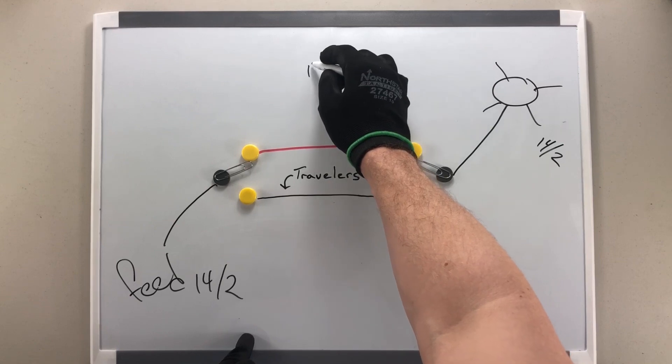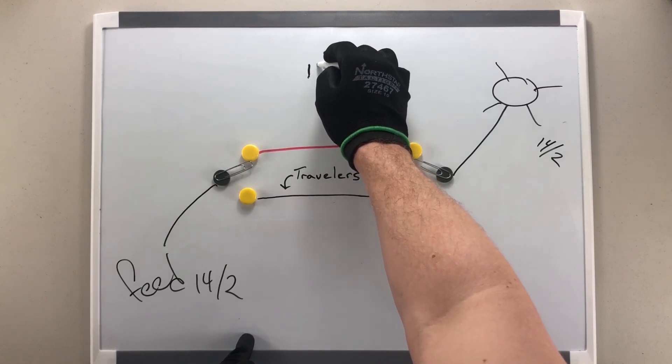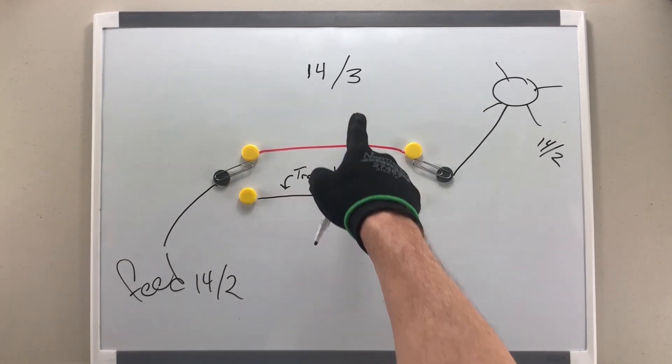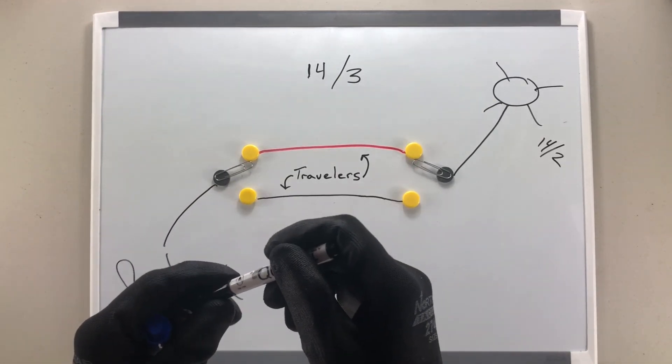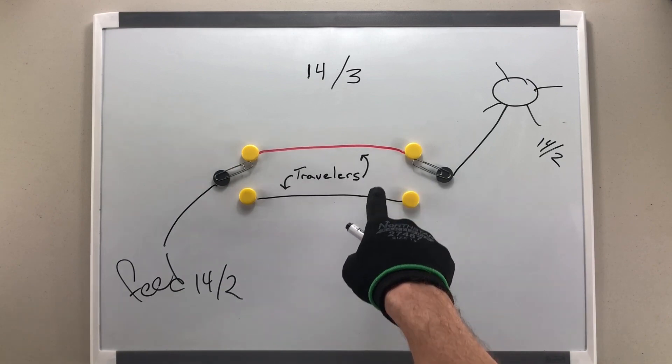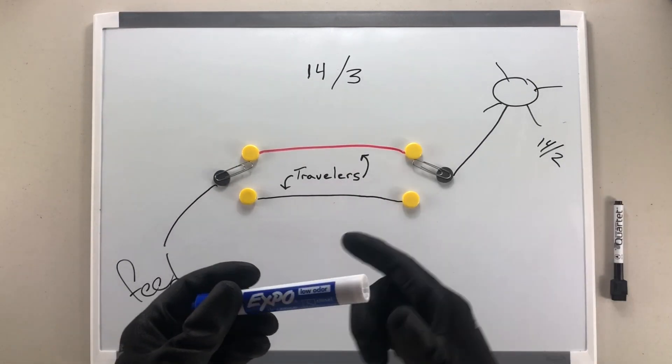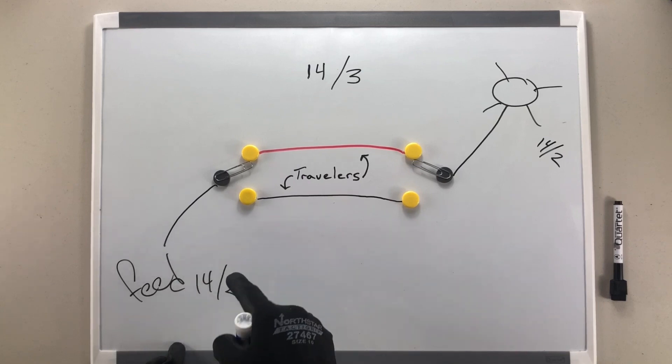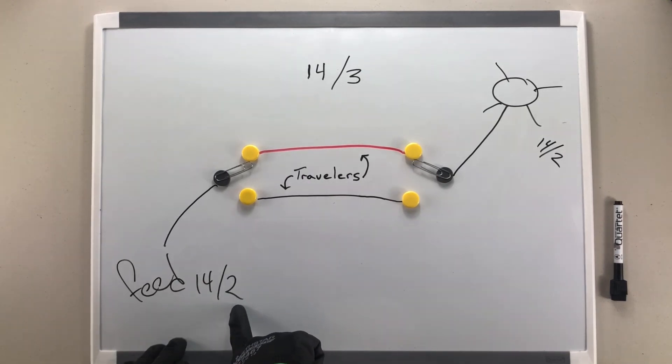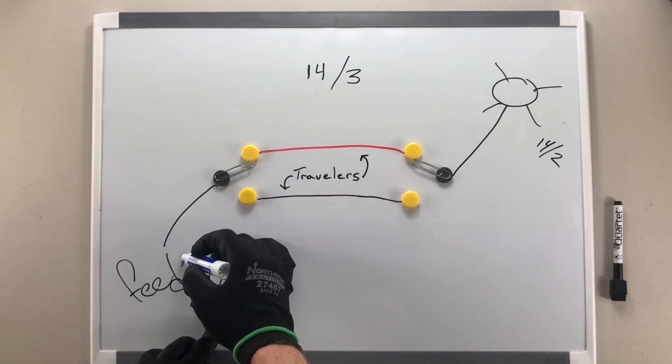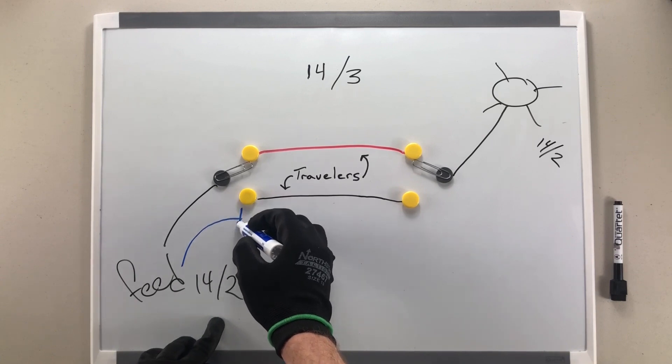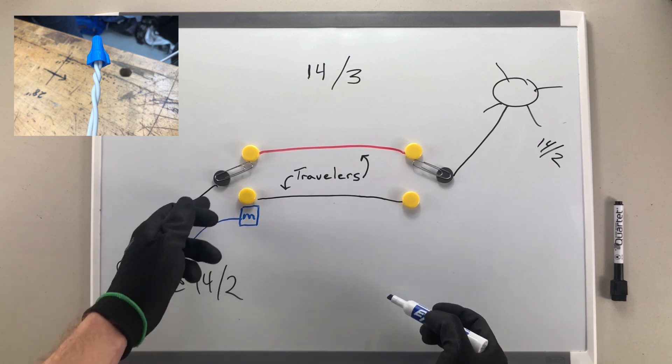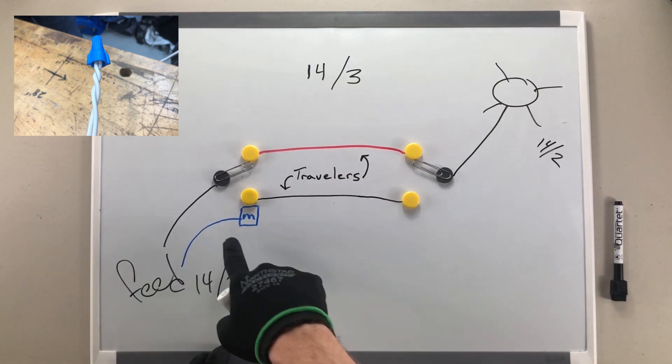Now, in the middle connecting these two, we have a 14-3 with three current carrying conductors. You see a red, a black, that's two of the three. The last one is a neutral. Our neutral from our feed, which will also be included in this two current carrying conductors here, will come up into this box, and we're actually just going to make a little wire nut connection here with our neutral.